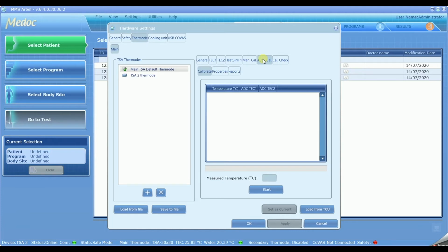So this is the most common procedure that you'll do in your track record with your Medoc device. The auto calibration is something that you just turn on and walk away from. During the auto calibration, the thermode will be checked on 30 points along the temperature range. Each point will be tested for about 2 minutes, so take into account that this whole procedure will take you about an hour. When you start the calibration, make sure that the thermode doesn't touch anything but the sensor, because during calibration, safety measures are off, and the thermode can get to extreme temperatures for a long time, so we don't want to have anybody's body touching the thermode.